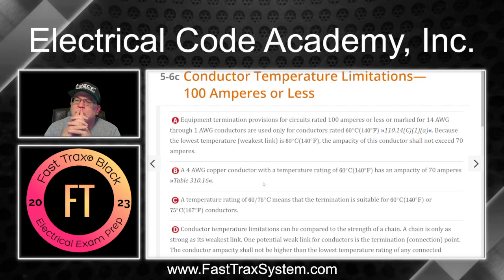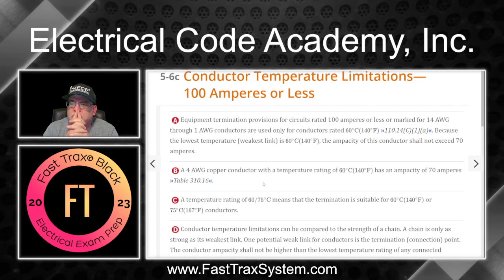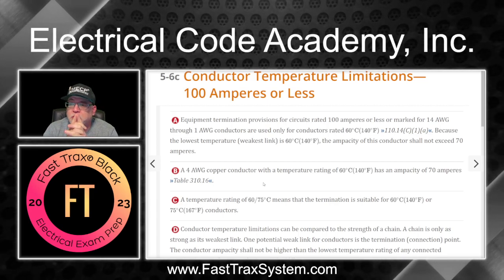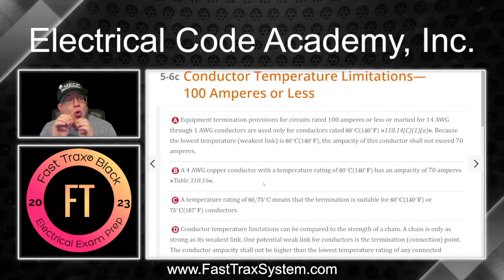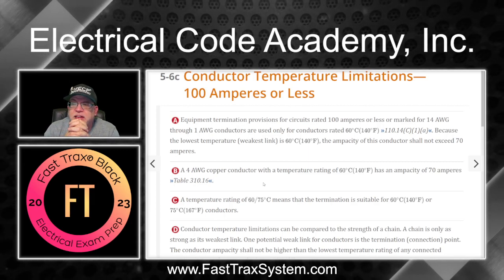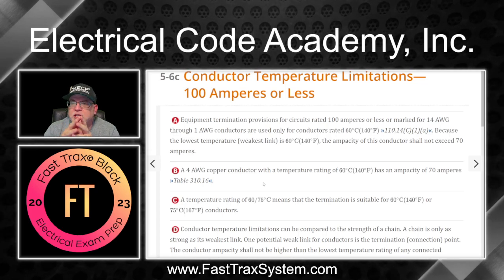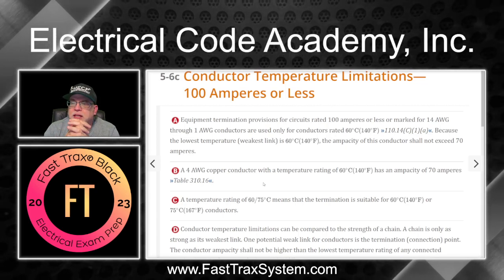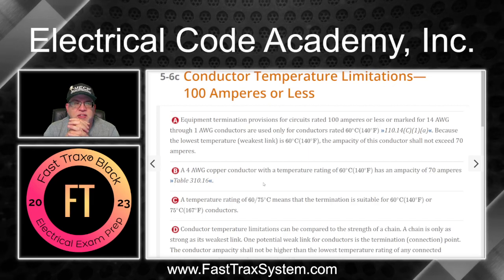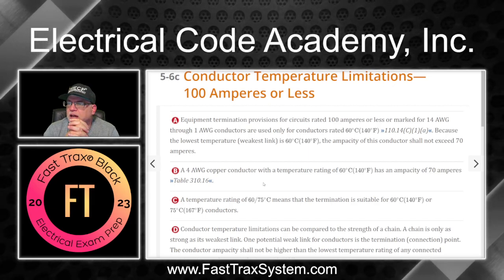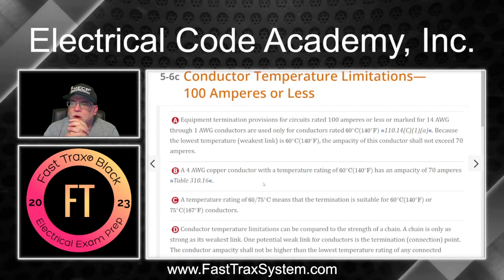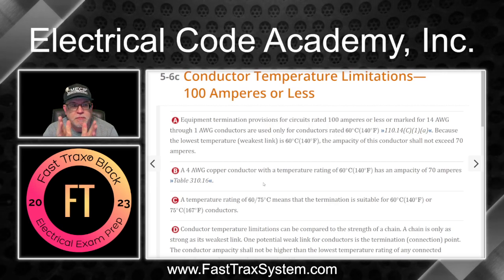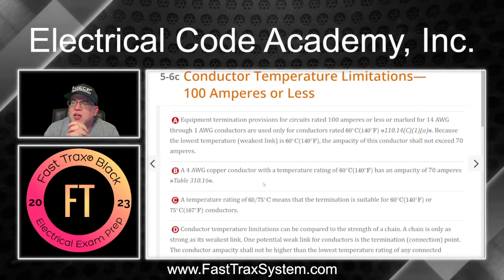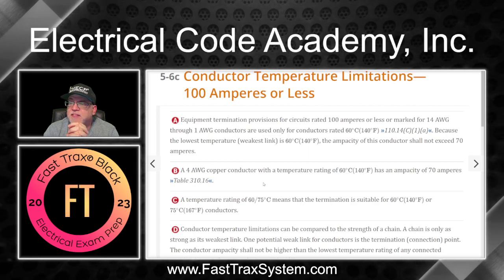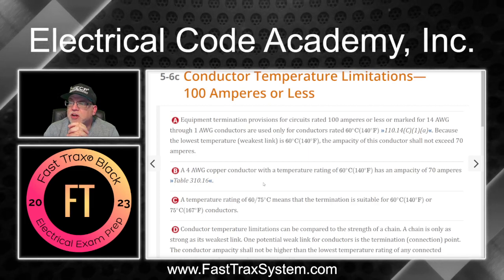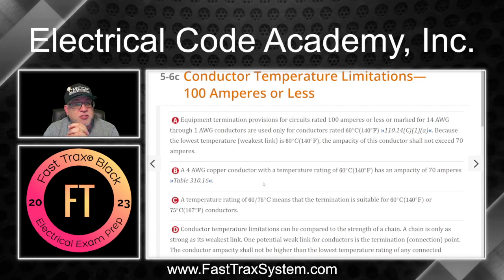What does A say? It says equipment termination provisions for circuits rated 100 amperes or less, or marked 14 AWG through 1 AWG, conductors are used only for conductors rated 60 degrees C, 140 degrees Fahrenheit, and that is told to us in 110.14(C)(1)(A). It says because the lowest temperature, the weakest link, is 60 C, the ampacity of a conductor shall not exceed 70 amperes.